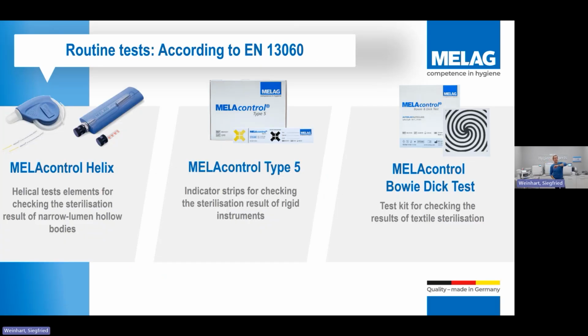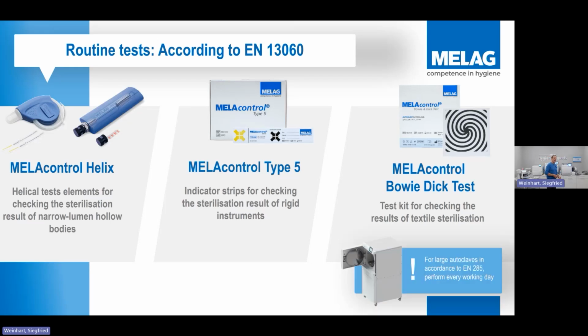Okay, and there are various other tests that you do. So you've got your helixes, you've got your type 5 indicator strips. Some autoclaves will use type 6 indicator strips. Non-vacuum, you'll do a type 6 indicator first cycle of the day. You've then got the Bowie Dick. Bowie Dick tend to be for any practices that are using textiles, things like that, to sterilize. It very much tends to be laboratories or veterinary or somewhere like that will use a Bowie Dick where they're putting textiles through the unit as well.